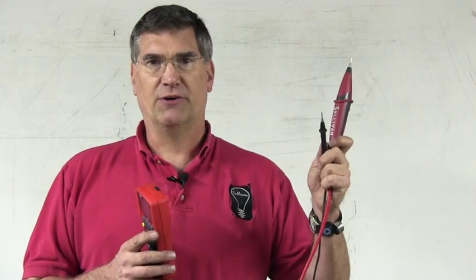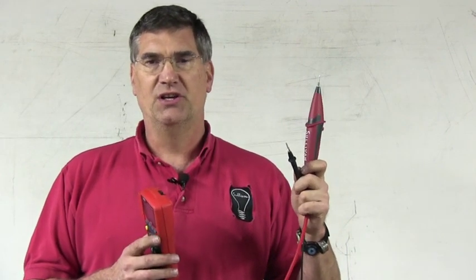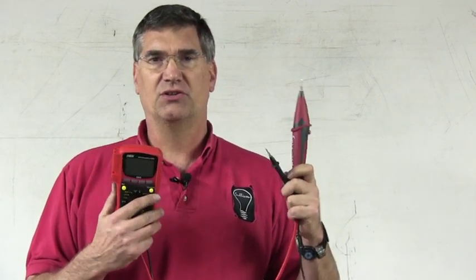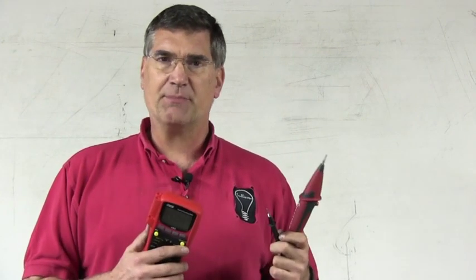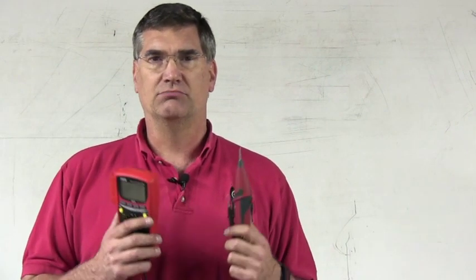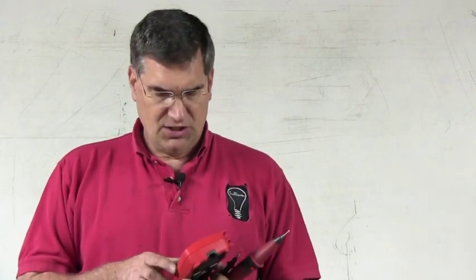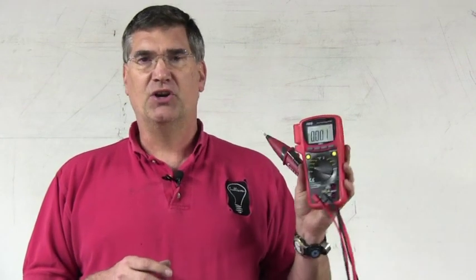Okay? Then you simply load the circuit with the Load Pro. And if there is a fault in the circuit caused by high resistance or corrosion, then what you'll see is you'll see the voltage drop. And when the voltage drops, that means that there is some other type of fault in the wiring, and you need to inspect the wiring before you go out there and you start changing parts. So a couple of things about the voltmeter you need to know before you go out there and use it.